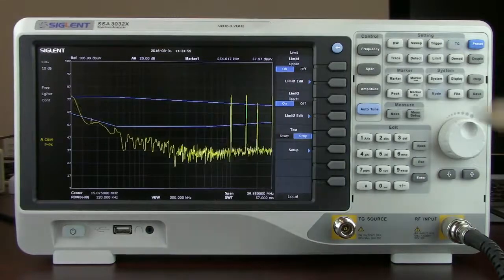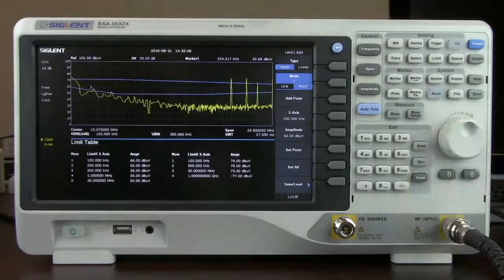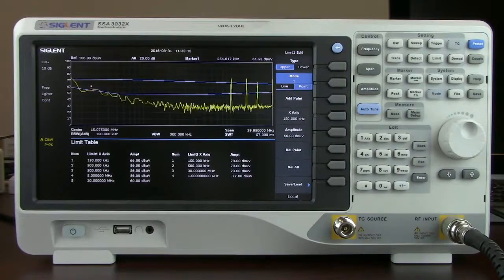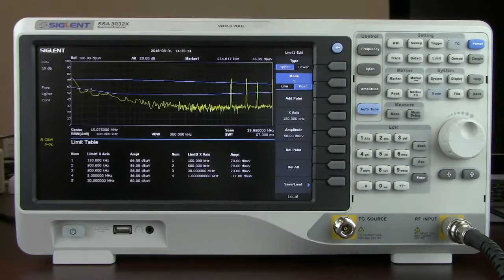Both of the limits can also be edited. They've got a line mode as well as a point mode. In the point mode, you can see we've got the X axis as well as the amplitude values for each of the points in that particular test. All of these features are very helpful when you're performing pre-compliance, and there's also a software application that can help to sequence a lot of the data collection.